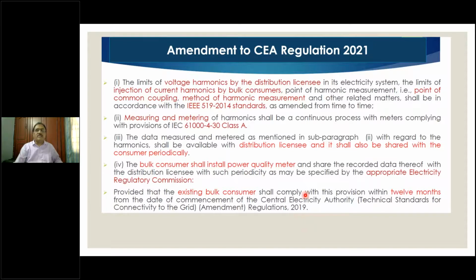So in this amendment, which was issued on 6 February 2019, they specifically talked about IEEE 519 2014 being the standard. The IEEE 519 1992 was the first time the standard came in the world for harmonics and power quality. The first amendment to that standard came in 2014. It had taken such a long time. Why? We are not going to discuss, but you can pursue and find out the actual reason for it.